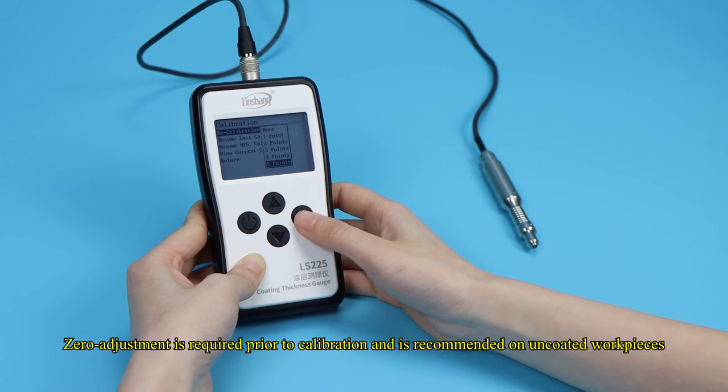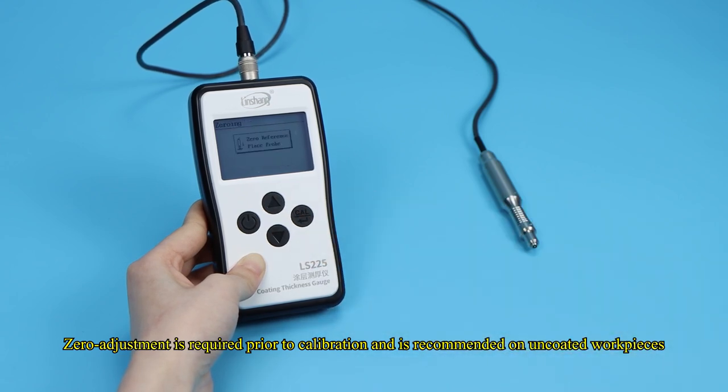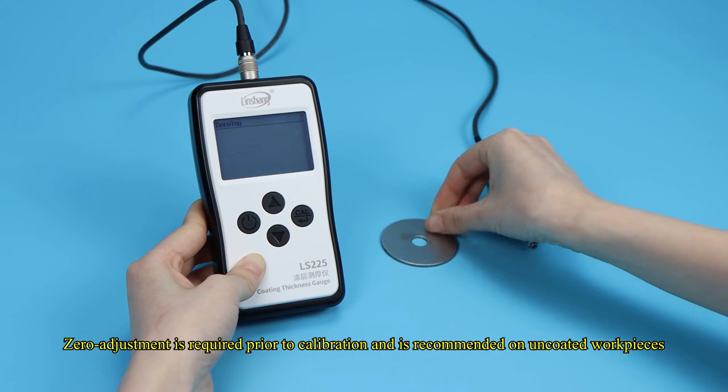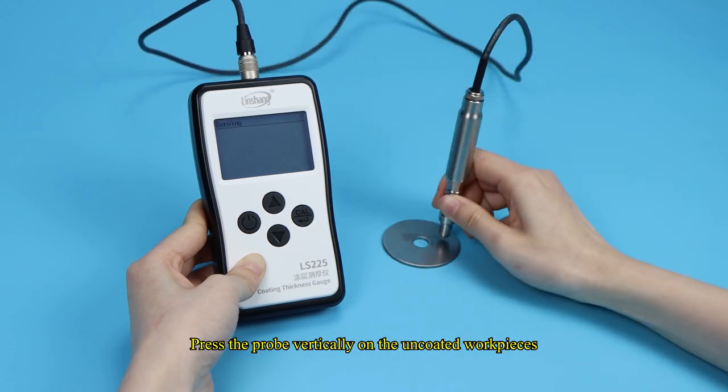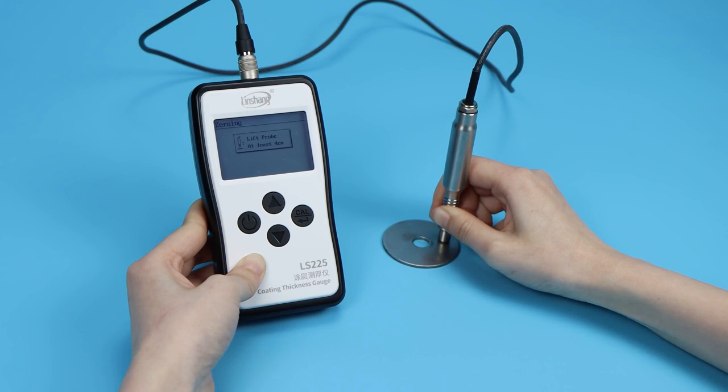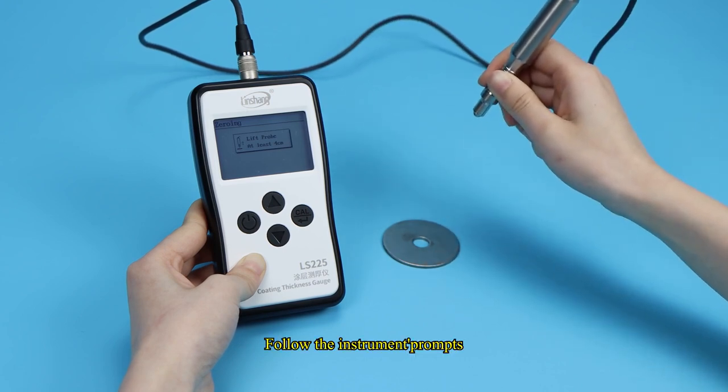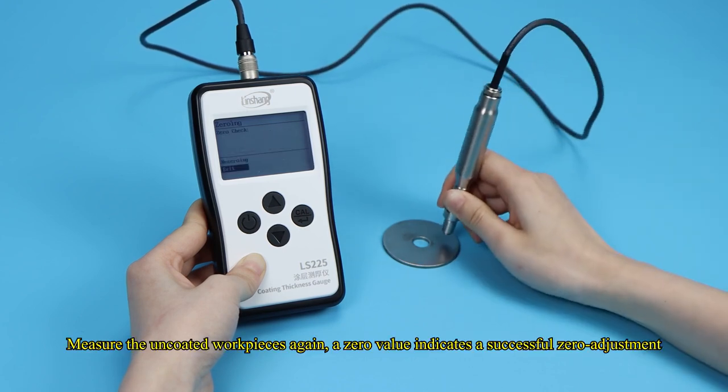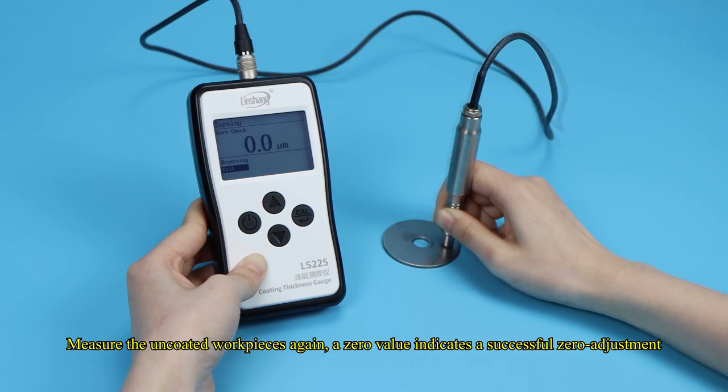Zero adjustment is required prior to calibration and is recommended on uncoated workpieces. Press the probe vertically on the uncoated workpieces. Follow the instrument prompts. Measure the uncoated workpieces again. A zero value indicates a successful zero adjustment.